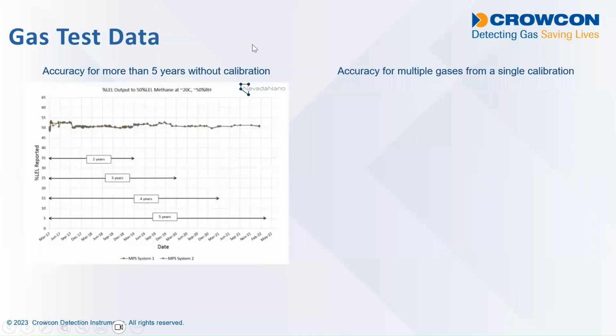Okay, before I run through the test data, we've got another question in the chat, which we'll just have a look at. Is there a standard life of a pellistor, and is there a large difference between the price of pellistor and MPS? So the life of a pellistor absolutely depends on the environment it's exposed to during its life. If you are in a very clean environment where there is no silicone, no lead, no sulfur compounds, it doesn't get exposed to much gas, then a pellistor might last 5 to 10 years. They can last a long time. However, in real life, most pellistors require replacing at least every 5 years, and in industrial applications, possibly down to 3 years. It all depends.